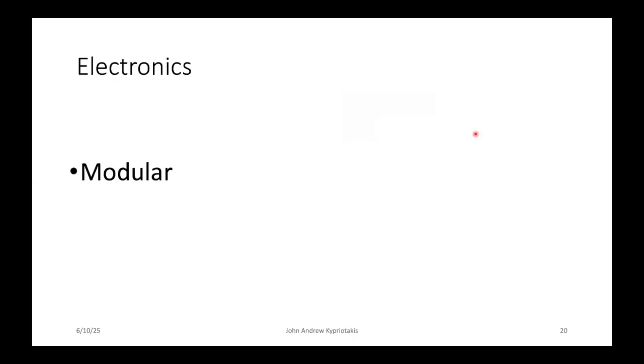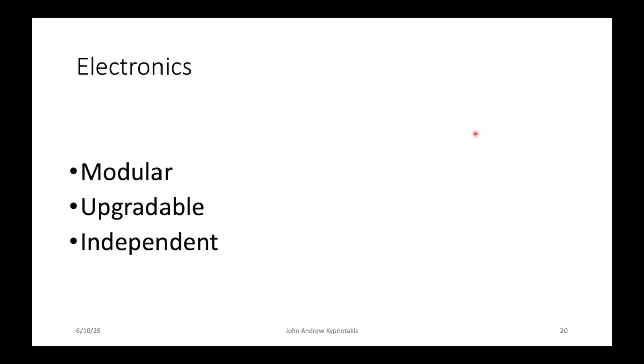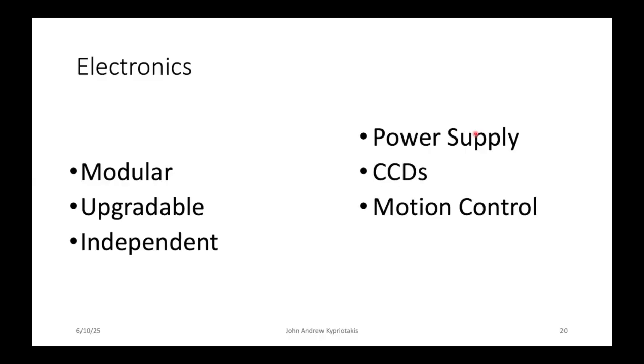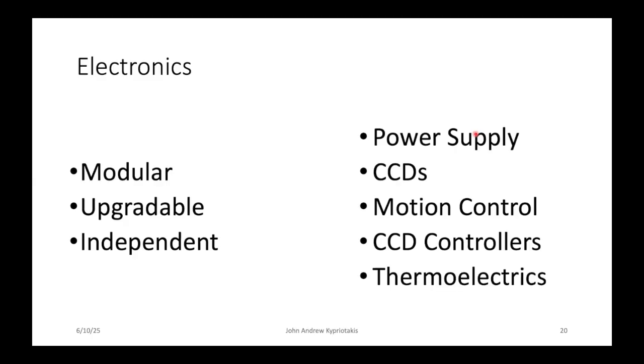Our electronics needed to be modular, so that means that every component is isolated and can be upgraded on its own. They need to be upgradable, so we need to be able to remove components and replace them as needed, and they need to be independent. So if one component breaks or fries, we can replace it without losing our instrument meanwhile. And we start with power supplies and CCDs to motion control cards, CCD controllers, and thermoelectrics. And I will analyze each of them in some detail.